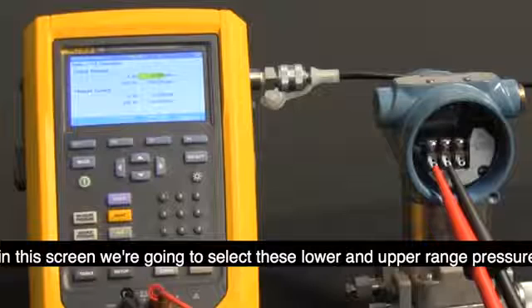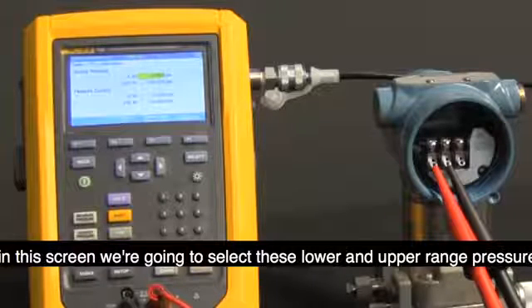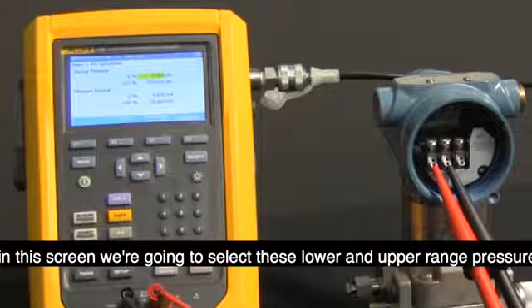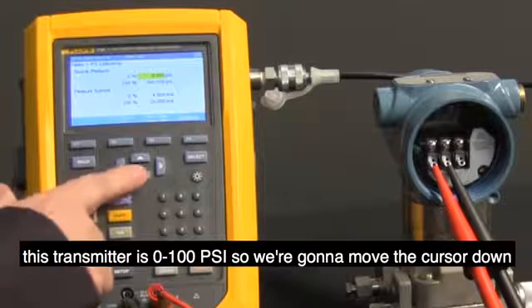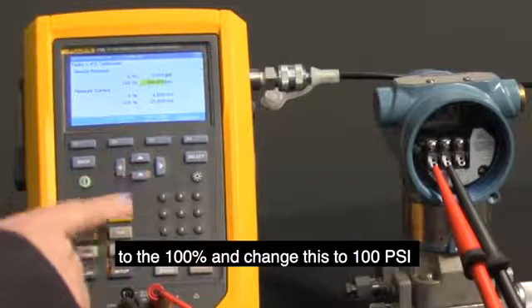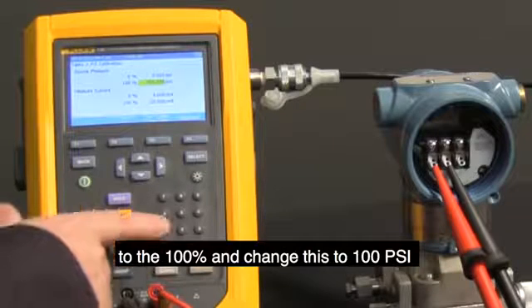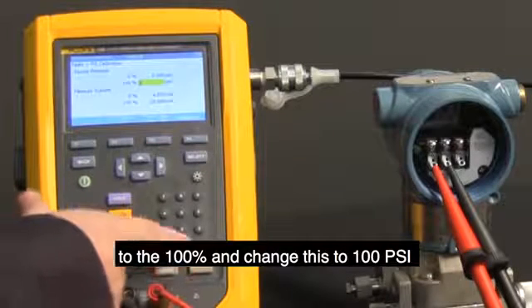In this screen, we're going to select the lower and upper range pressure. This transmitter is 0 to 100 psi, so we're going to move the cursor down to the 100% and change this to 100 psi.